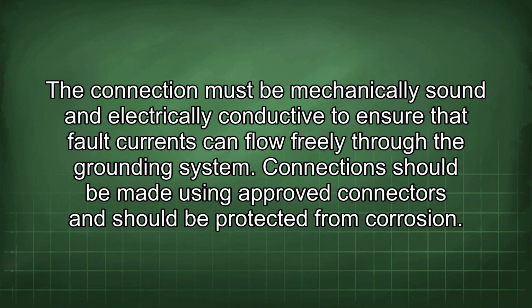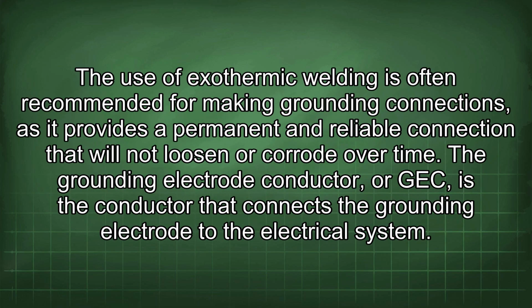The connection must be mechanically sound and electrically conductive to ensure that fault currents can flow freely through the grounding system. Connections should be made using approved connectors and should be protected from corrosion. The use of exothermic welding is often recommended for making grounding connections, as it provides a permanent and reliable connection that will not loosen or corrode over time.